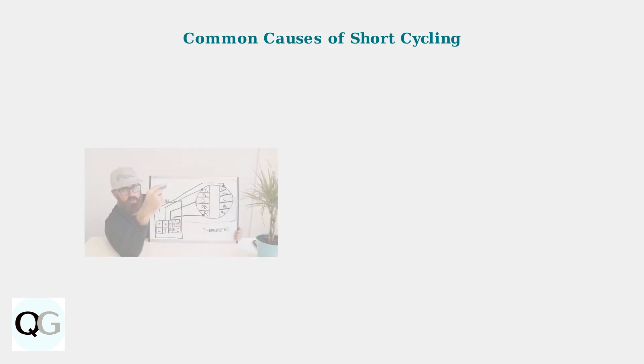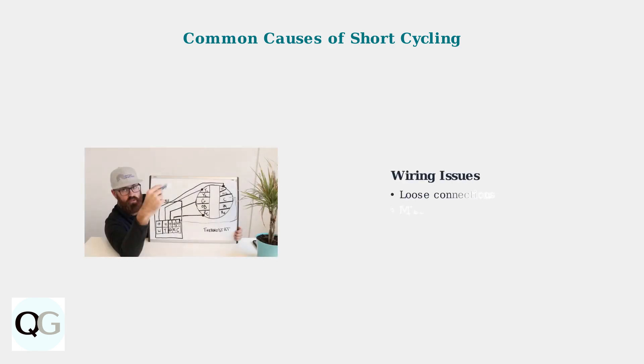Several factors can cause short cycling in Nest thermostats. Understanding these causes helps you identify the root problem. Wiring problems are a leading cause of short cycling. Loose connections, missing common wires, or incorrect wiring can disrupt communication between your thermostat and HVAC system.